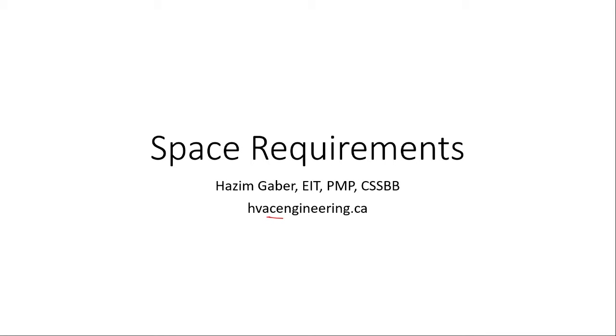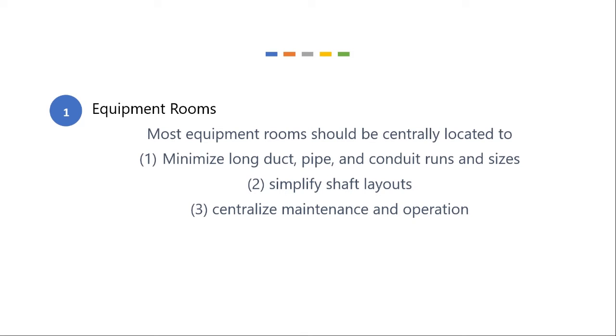So today we're going to talk about space requirements. How much space do you need for your HVAC equipment? Typically, mechanical and electrical space requirements are between 6 and 9% of the gross building area, and they can be as low as 4%. So when you design HVAC, you need to consider equipment rooms that are centrally located.